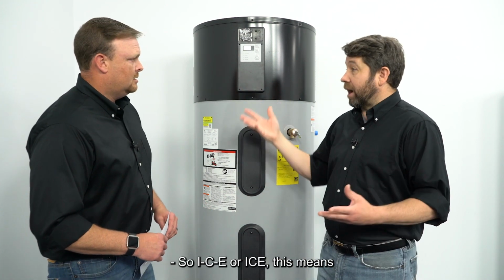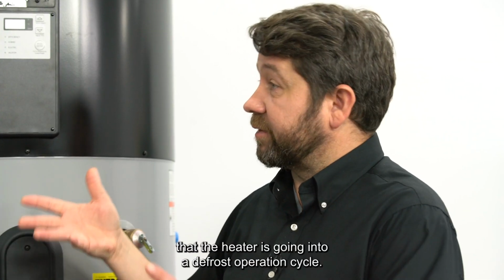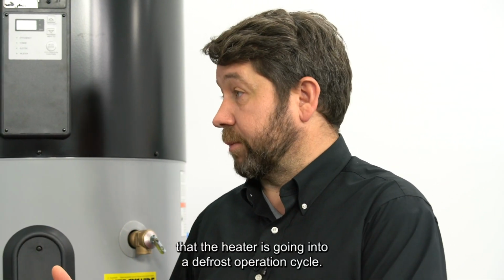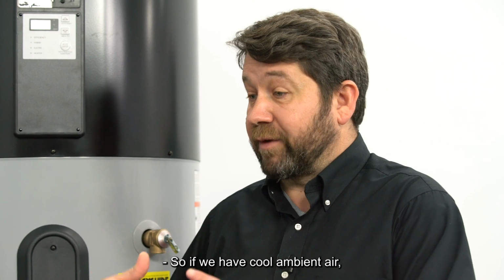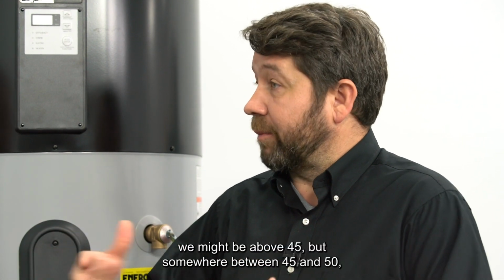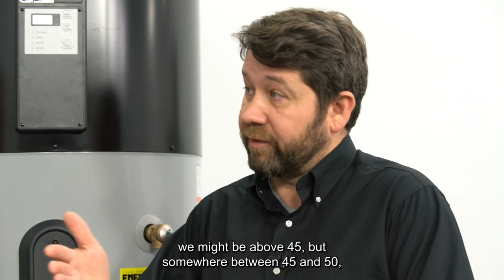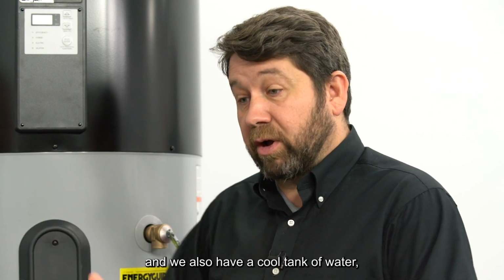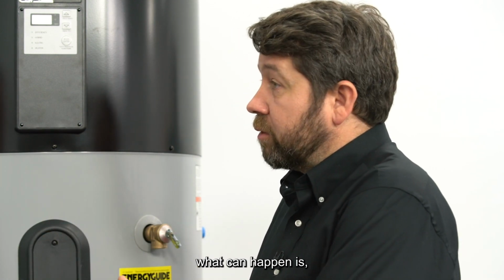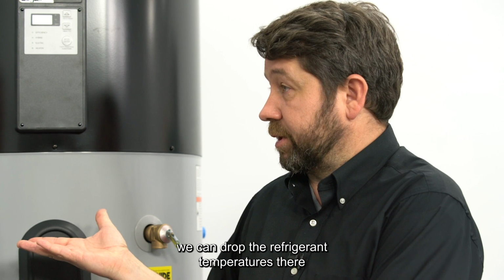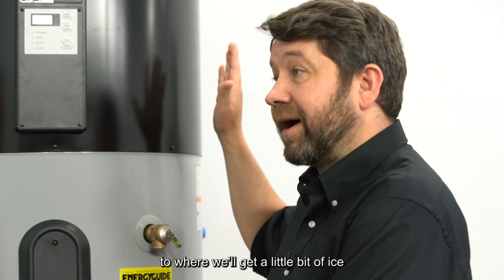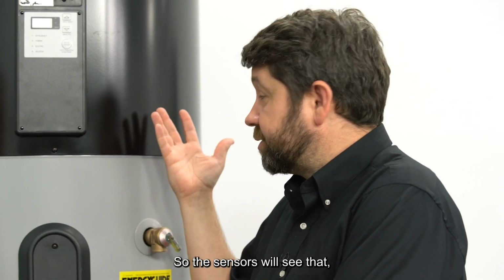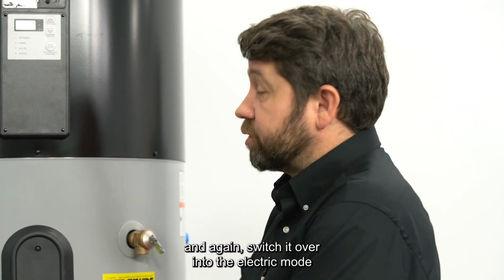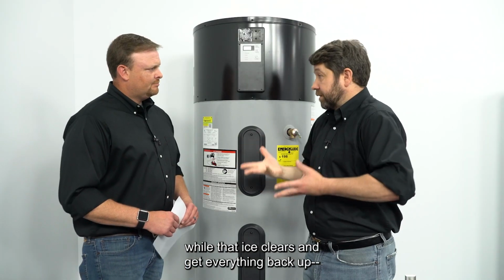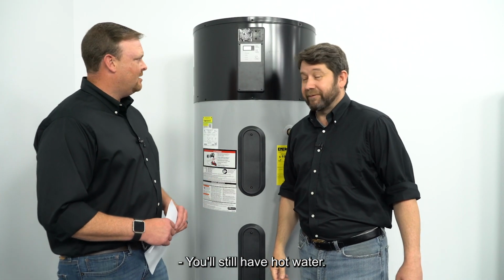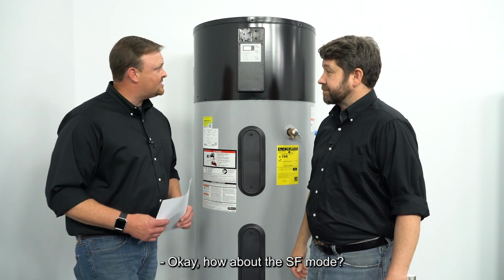Okay, how about ICE? So ICE means that the heater is going into a defrost operation cycle. If we have a cool ambient air, we might be above 45, but somewhere between 45 and 50, and we also have a cool tank of water, what can happen is we can drop the refrigerant temperatures to where we'll get a little bit of ice that will form on that coil. So the sensors will see that, and again, switch it over into the electric mode while that ice clears and get everything back up into the right range. Still have hot water.